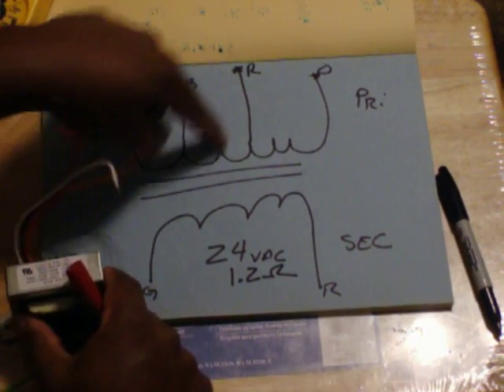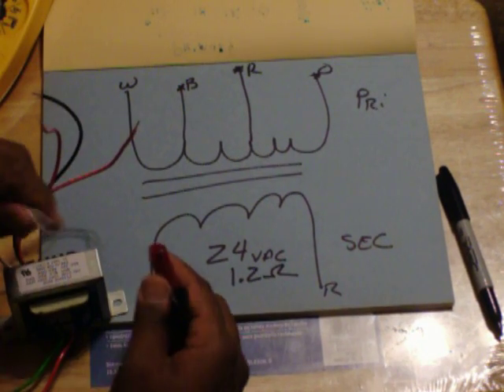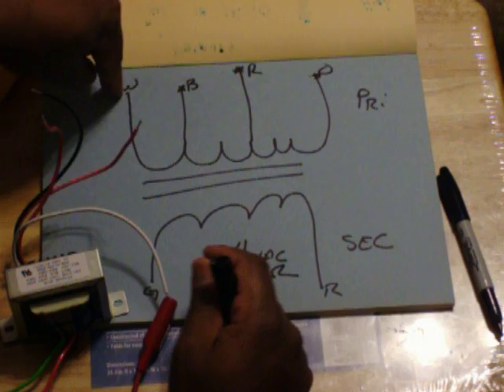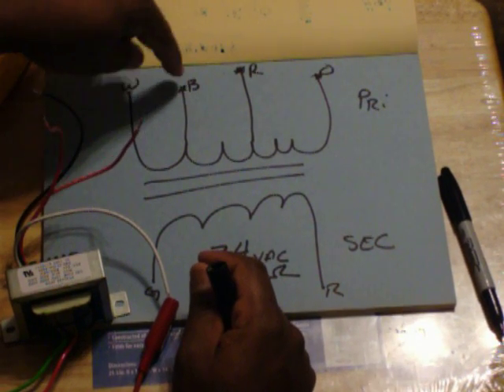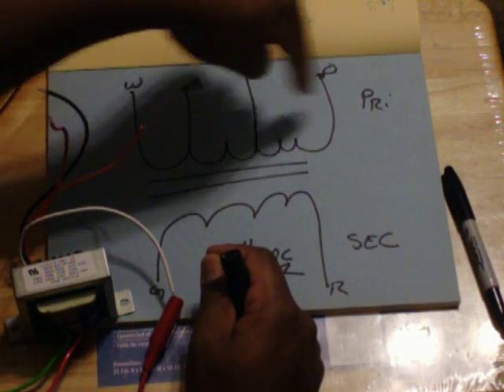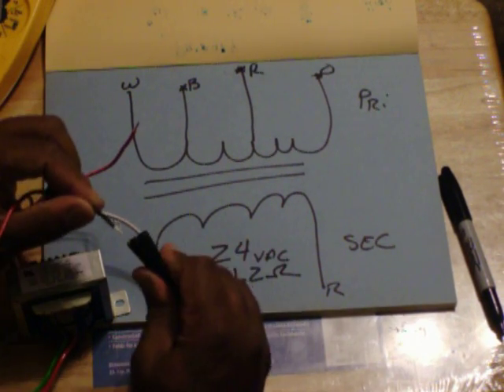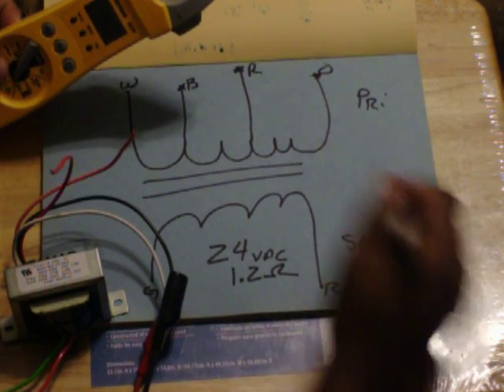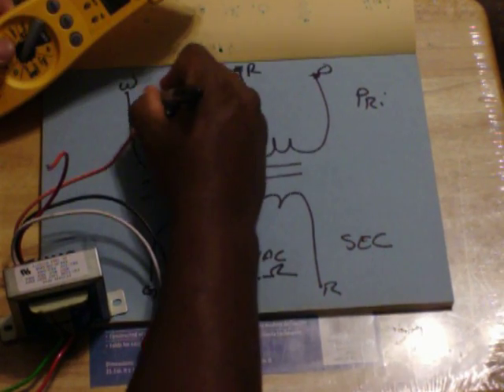Now, to check the primary side, we're going to clip on this white wire here. And I'm actually never going to move that one. I'm going to check white to black, white to red, white to orange. And as I go, the resistance should increase. White to black. 19.9, let's just say 20 ohms.